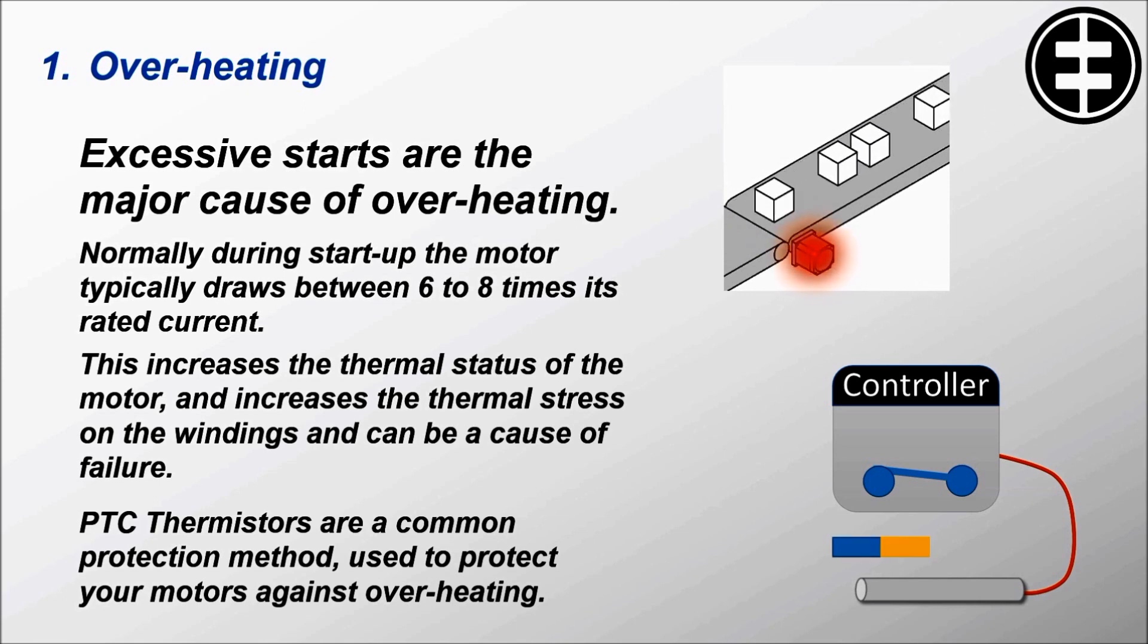PTC thermistors are a common protection method used to protect your motors against overheating. Thermistors have a positive temperature coefficient, meaning that the resistance is increasing rapidly around the trip temperature. Connected to a thermistor relay, this will trip preventing overheating.